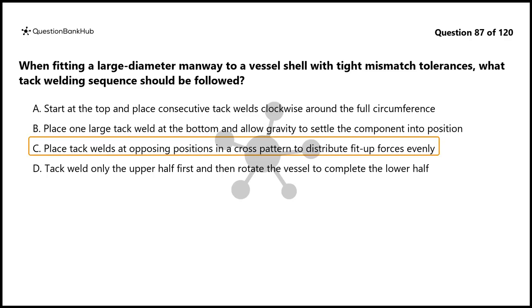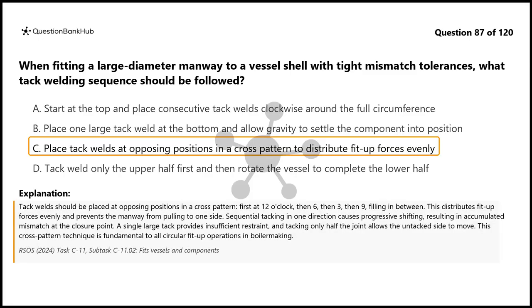The correct answer is C. Tack welds should be placed at opposing positions in a cross pattern, first at 12 o'clock, then 6, then 3, then 9, filling in between. This distributes fit-up forces evenly and prevents the manway from pulling to one side. Sequential tacking in one direction causes progressive shifting, resulting in accumulated mismatch at the closure point. A single large tack provides insufficient restraint, and tacking only half the joint allows the untacked side to move. This cross-pattern technique is fundamental to all circular fit-up operations in boiler making.